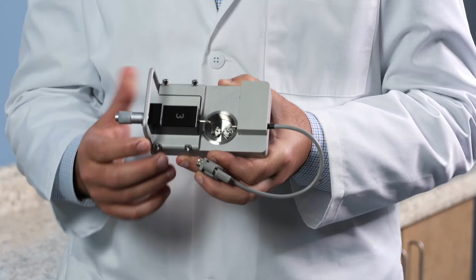There is a pH port for an optional pH probe to measure the real-time pH in your chambers, as well as an RS-232 connection for factory diagnostics, a slot for a temperature probe, as well as a ground port to eliminate electrical noise. When looking at the chamber itself, you will notice there are 2 mounts in the tissue chamber.